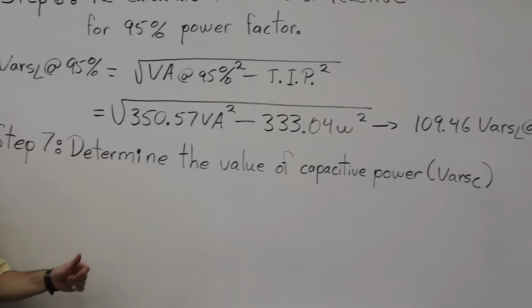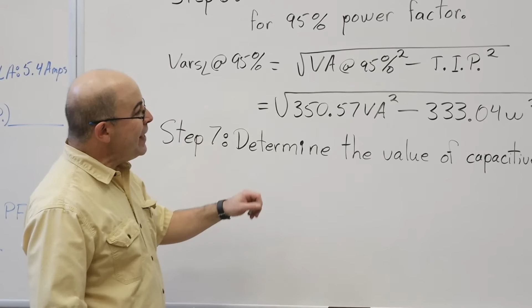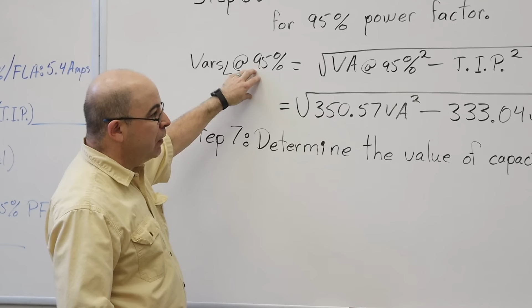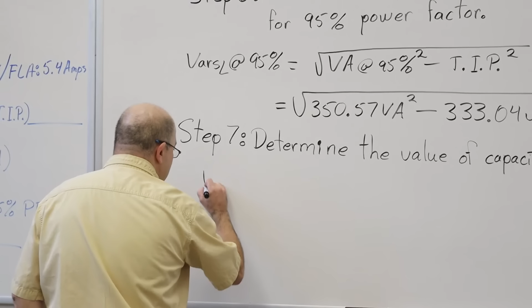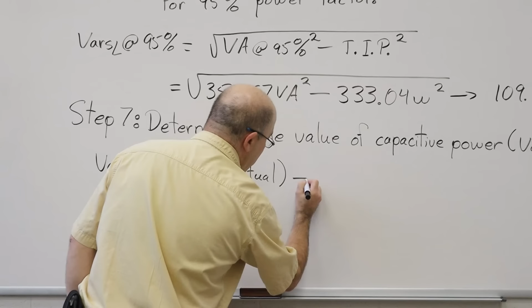Our next step is to figure out how much reactive power is going to come from the capacitor. I'm going to use the value of reactive power from our previous calculations as well as the actual value of reactive power. The formula looks like this: VARs_C equals VARs actual minus VARs_L at 95%. There's no trig formula here, it's just a straight subtraction.